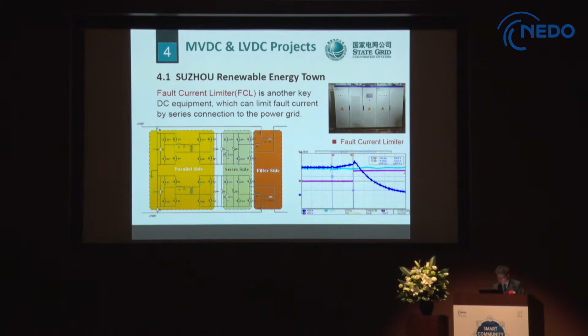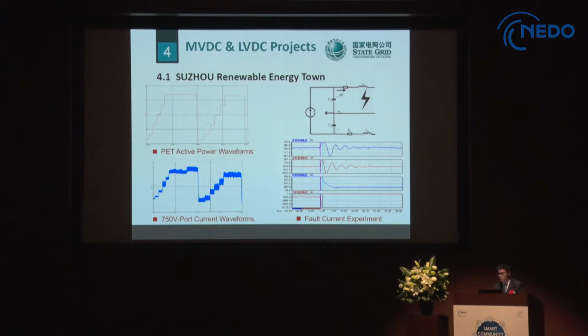about the operation of the Suzhou Energy Town. The left one is the PET active power waveforms, and the 750 volt port current waveform under different operation conditions. And the right one is a pole-to-pole fault experiment. When we did the fault experiment, the fault current achieved 2,100 amperes, which is caused by the capacitor discharge process, because large capacitors are paralleled at the DC bus. When a fault happened, the discharge process of the capacitor caused a large inrush current, which is seen here, about 2,100 amperes. So DC breakers are very important in the DC power grid.